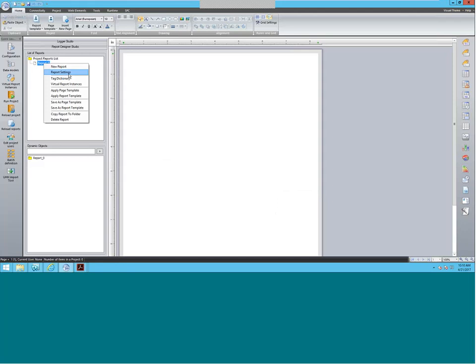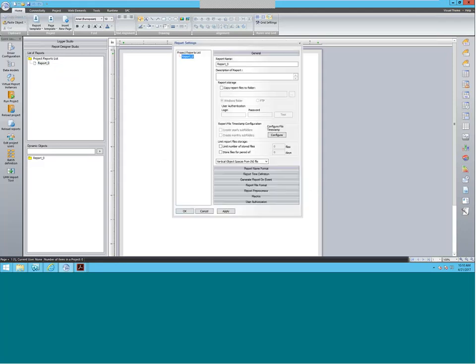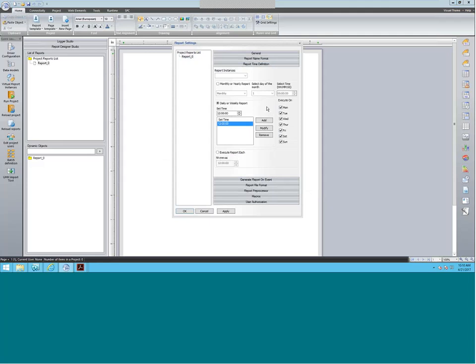Next, we're going to do some report settings. Going into report settings, we can rename the report — I'm going to name this one Reactor Report. You can put a description to the report if you have multiple that are the same. And then we have report time definition. This setting allows us to output the report at any given time that we set — at a certain time of the month, a yearly report, or do an execution every hour, every minute, or every second if you need that granularity.